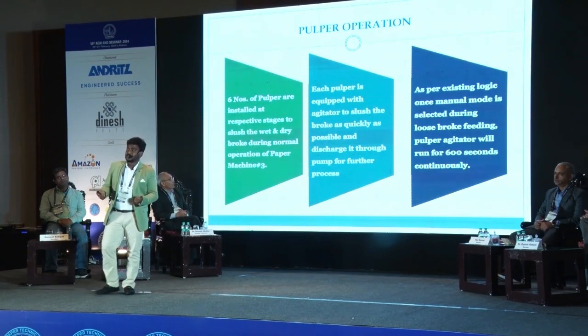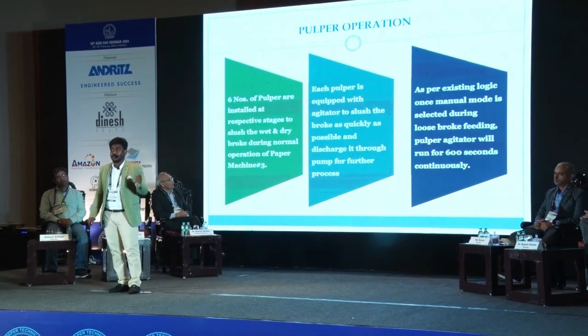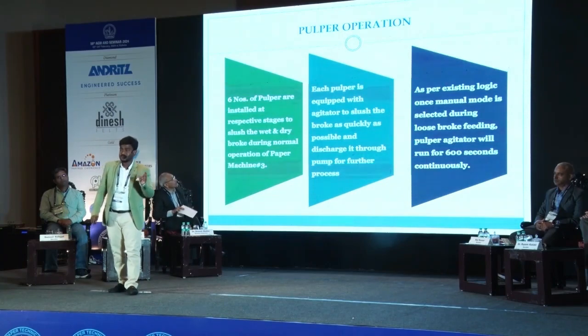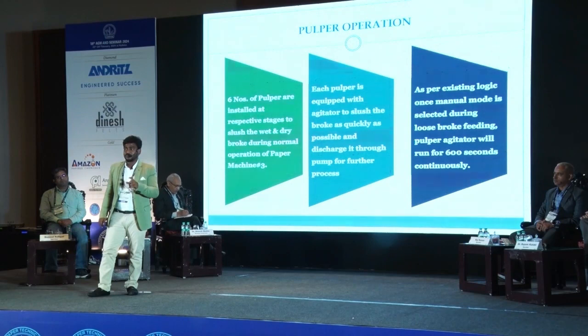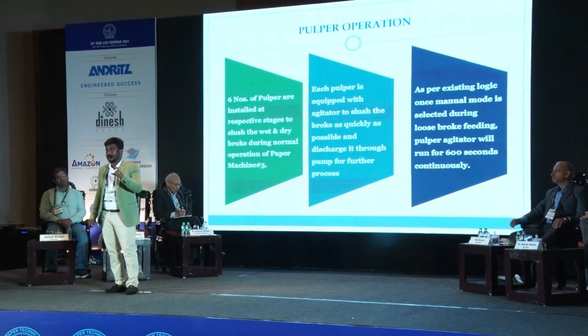So as per the existing logic, we observed that whenever the pulper is taken in manual mode, the agitator would run for 600 seconds continuously before it goes off. The pulper is equipped with a 315 kilowatt agitator motor. So every time it gets on, this agitator would run for 600 seconds continuously before it goes off.